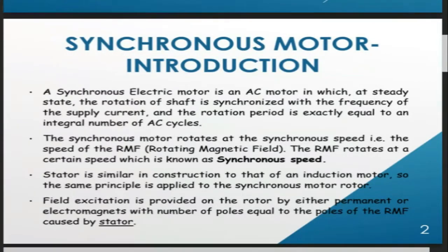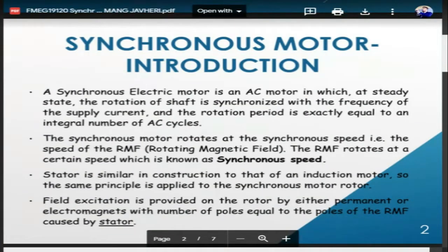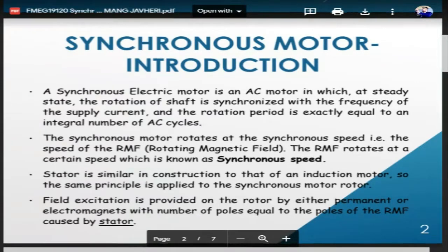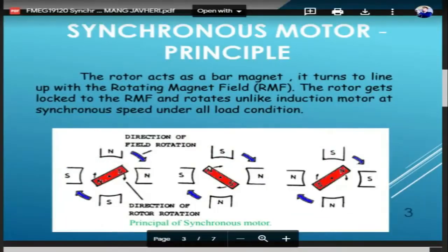Another advantage of the synchronous motor is excitation-based power factor control. If the magnetic field strength of the rotor is increased, the motor will possess a different power factor. Similarly, if we reduce the rotor magnetic field strength, we get a different power factor — either lagging or leading.